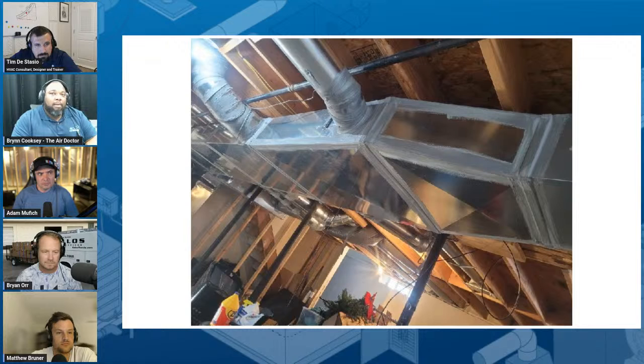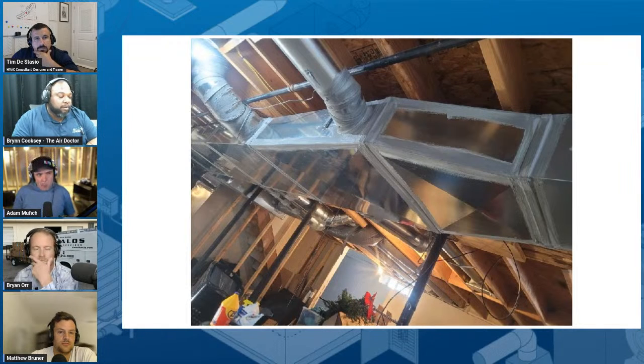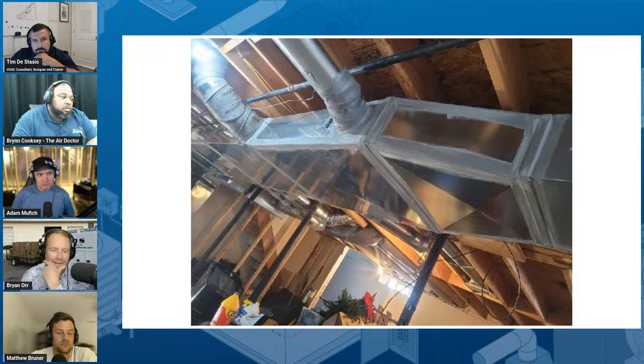So we'll pull the blower motor out physically. The techs will get in there and actually look from the bottom to see if they have any kind of cracks or anything like that. And we find them, I'll say 90% of the time, they're physical giant cracks that you couldn't see maybe from sticking an inspection camera through a limit or looking at it from the top. But if we pull a blower motor out, we typically find them with neglect and high airflow, poor airflow situations. Which is exactly what we're talking about here.